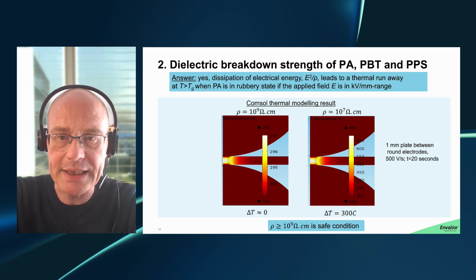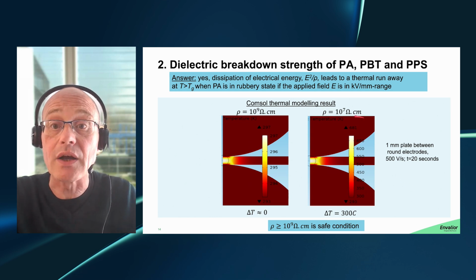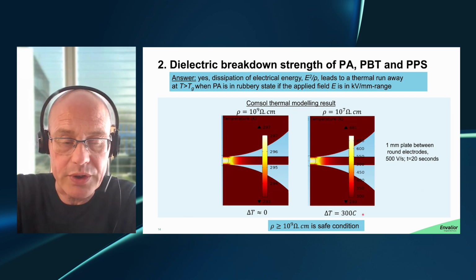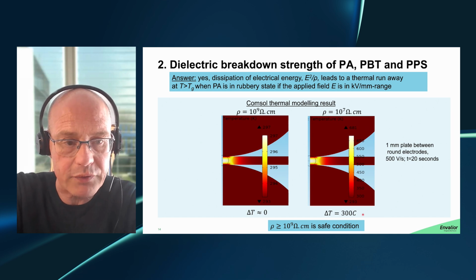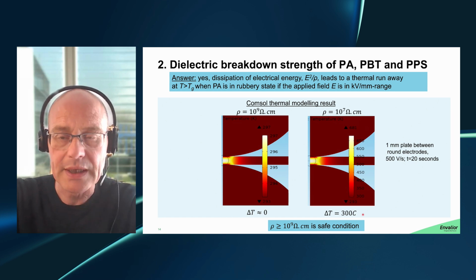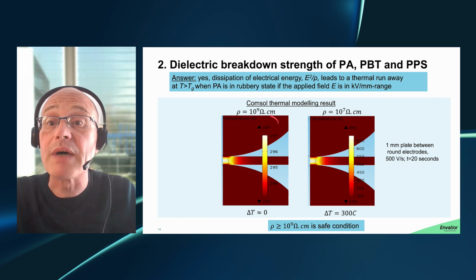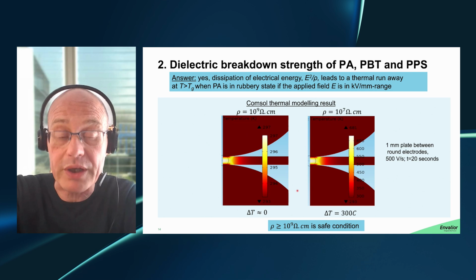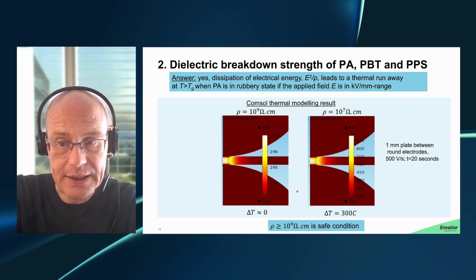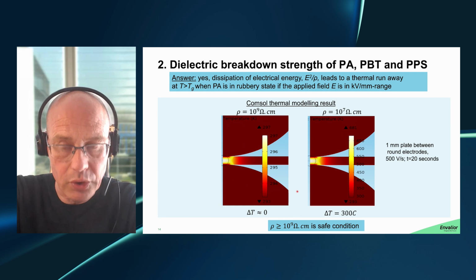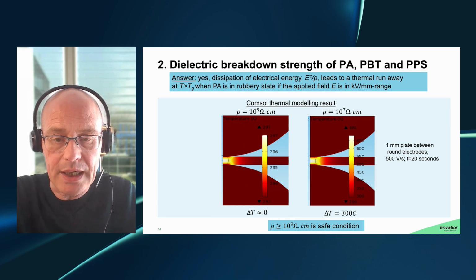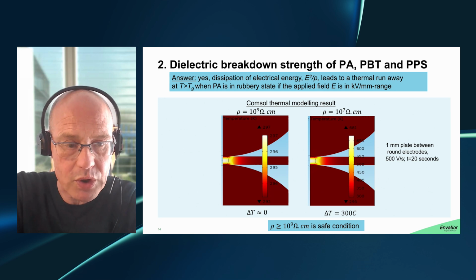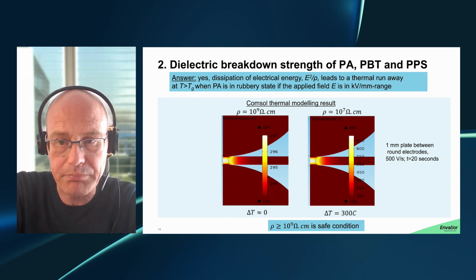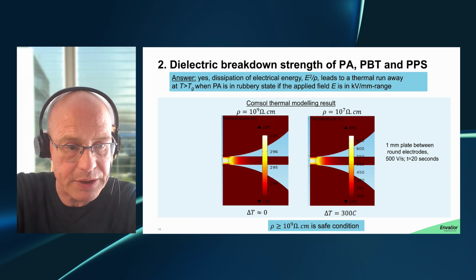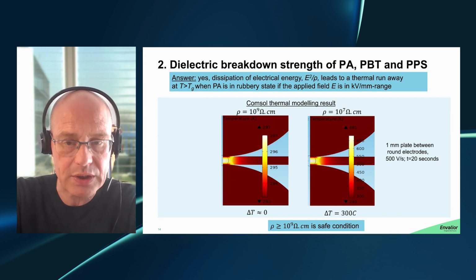And what you indeed see is that if the resistance is lower, there's a big temperature increase leading to degradation and destruction of the material, a breakdown. If the resistance is high enough, so above 10 to the power 9 ohms times centimeter, that heat up does not occur and you're essentially in a safe zone. So indeed, if the resistance drops below 10 to the power 9 ohms times centimeter, these thermal breakdowns do occur.